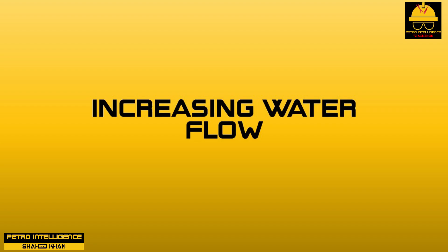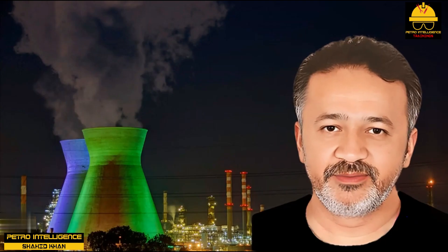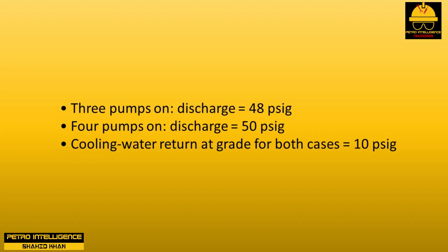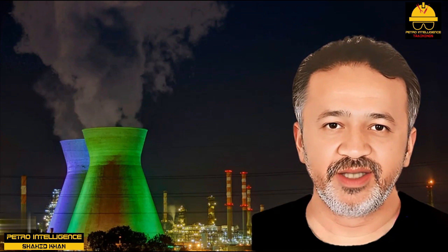Increasing water flow: your cooling tower basin is likely served by a number of circulation supply pumps. Putting an additional pump online does very little to increase the combined pump discharge pressure, meaning total water flow has not increased significantly. For example: three pumps give 48 psig discharge, four pumps give 50 psig discharge. With a cooling water return of 10 psig, the delta P for three pumps is 38 psig and for four pumps is 40 psig.